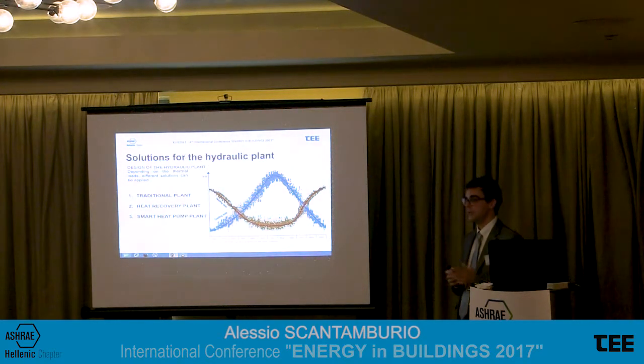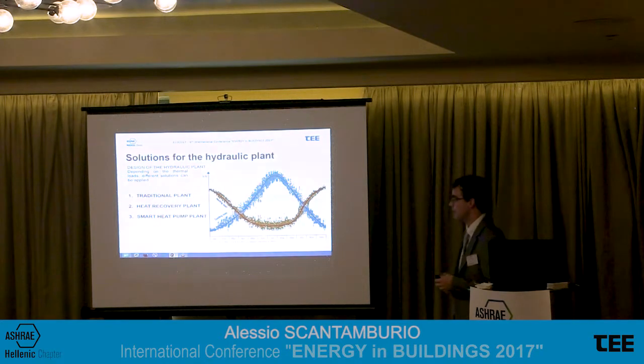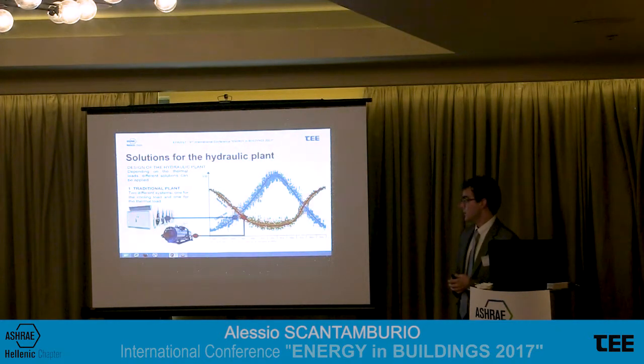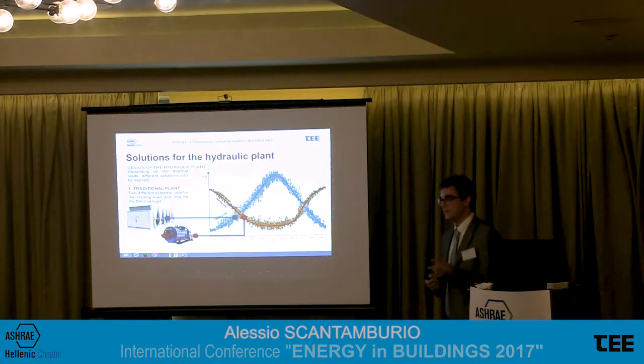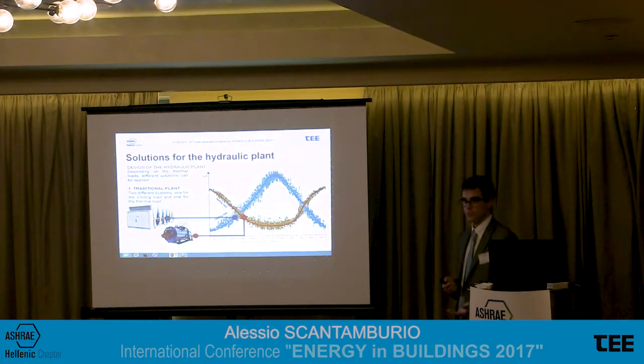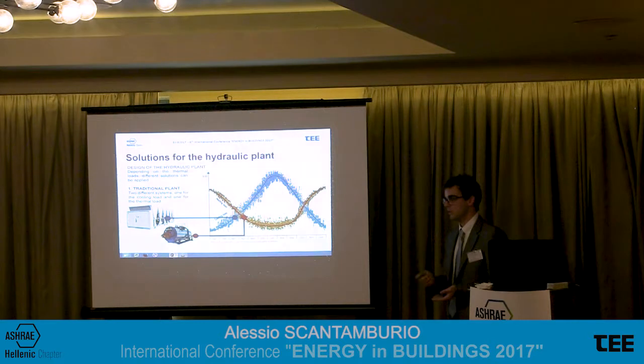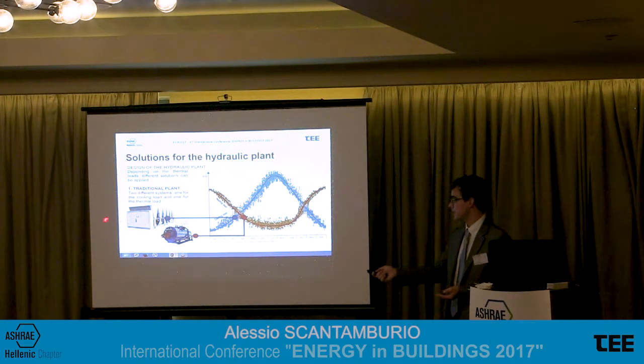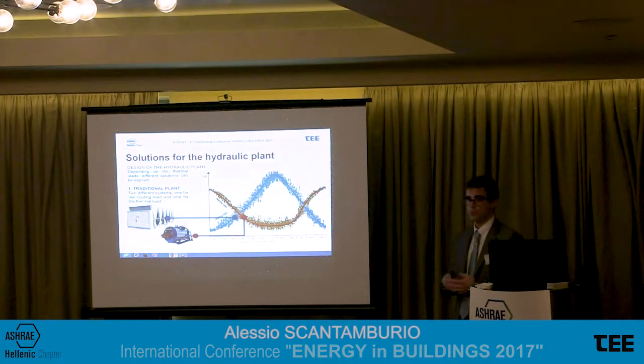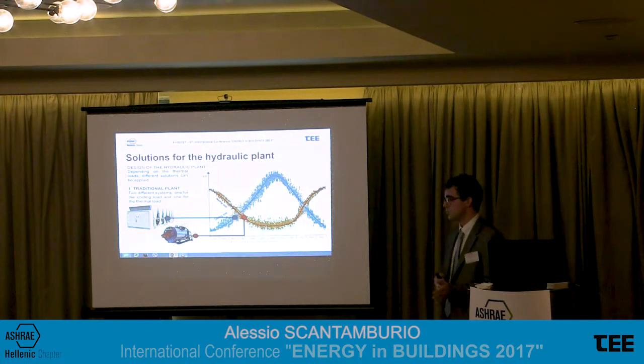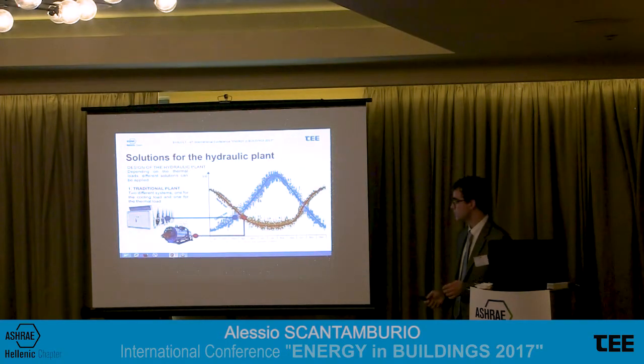We have 3 main possibilities: a traditional plant, a heat recovery plant, and the smart heat pump, 4-pipe plant. The traditional plant uses 2 completely different technologies to produce: one for producing cold water, typically a chiller, air-cooled, water-cooled, whatever, and a separate system, typically a gas boiler, to produce hot water. So 2 completely separated systems that work on their own.